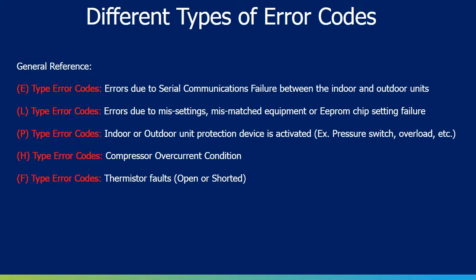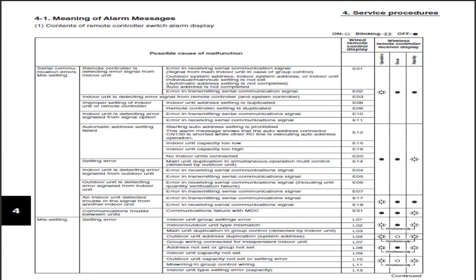This slide gives a general reference of the 5 different error codes which can occur and the general meaning of each error code. Always refer to the Service Technical Manual for all the detailed error code information. The following 2 slides are a full listing of all the error codes and their meanings. There are 2 columns to the far right. The first one shows how the error code would be displayed when utilizing the wired remote controller, and the second one shows the error codes when utilizing the wireless remote controller. As seen from this chart, the wired remote controller displays the exact error code where the wireless remote controller shows several possibilities, especially when dealing with E-type error codes.